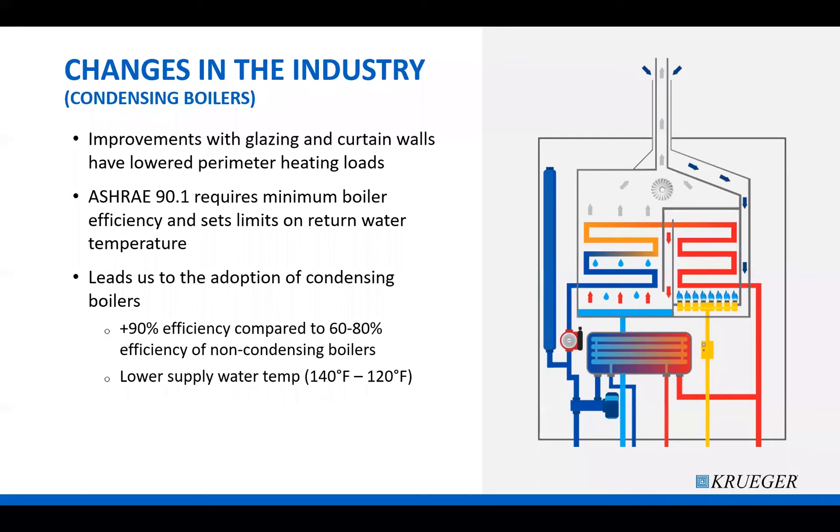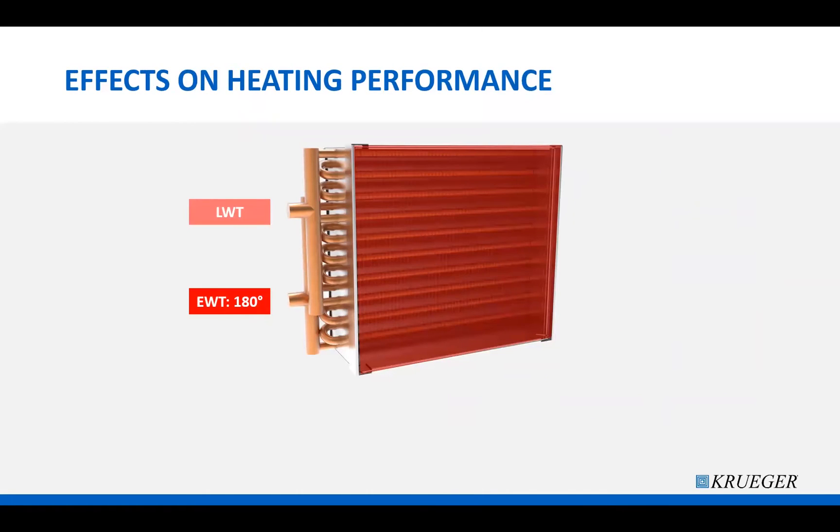Condensing boilers are also built to supply lower water temperatures. I've seen supply water temperatures from a boiler between 100 to 140 degrees, compared to the traditional 180 degrees, and this change helps improve the efficiency of the condensing boiler. While 180-degree entering water temperature is very easy to work with to supply necessary heating capacity on terminal units, lowering the water temperature drastically changes the heating performance of the hot water coils.